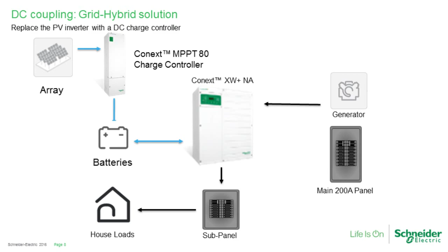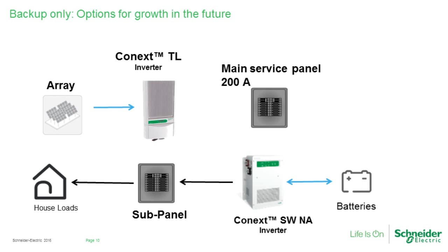A third option, of course, is what if it doesn't make sense or it's not possible to do an AC coupling retrofit? So this is where we can actually bring in energy storage along with the Conext SW and just simply provide backup power to those household loads. This can be a very, very easy way to manage a backup system when and if it doesn't make sense to actually bring in an AC coupling solution. So in this example here, of course, we have the Conext SW and the batteries, but what happens when we lose grid? Of course, the Conext inverter or the PV inverter is no longer connected to the grid, so it turns off. But we still have uninterrupted or nearly uninterrupted power to those household loads. And so this makes for an ideal solution when backup is needed, but it just doesn't make sense, again, to do that with an AC coupling solution.